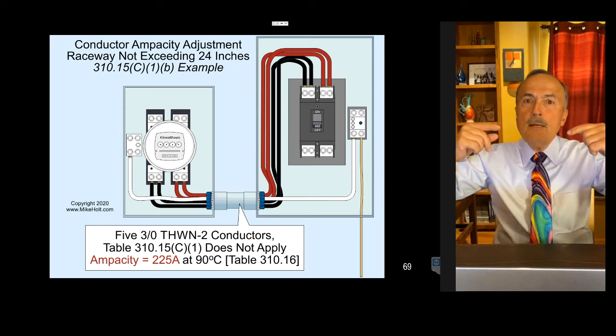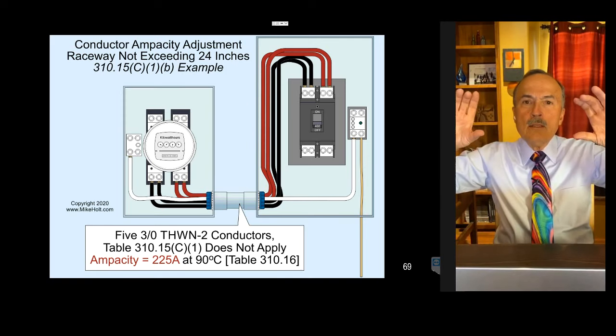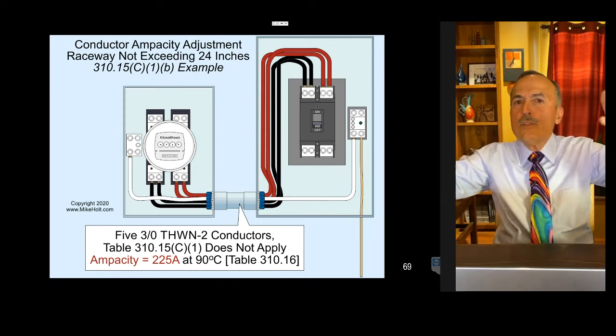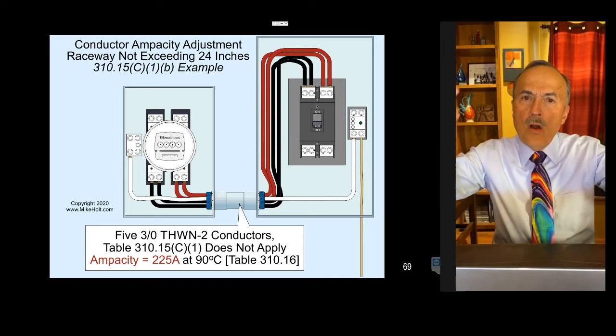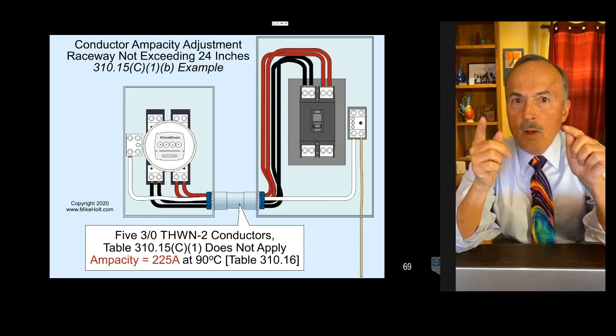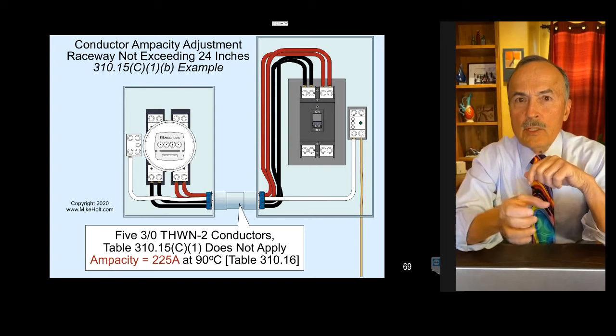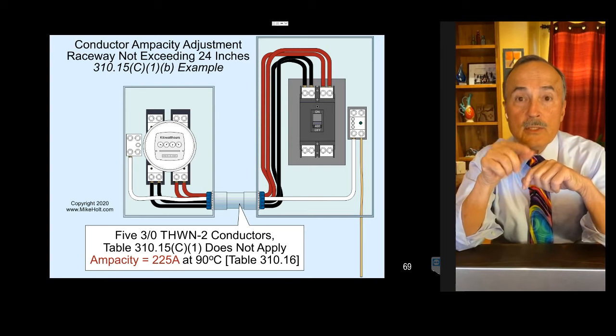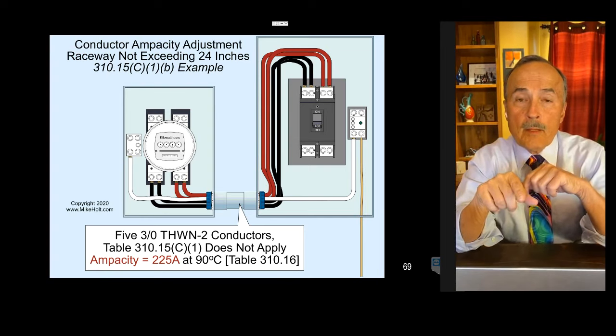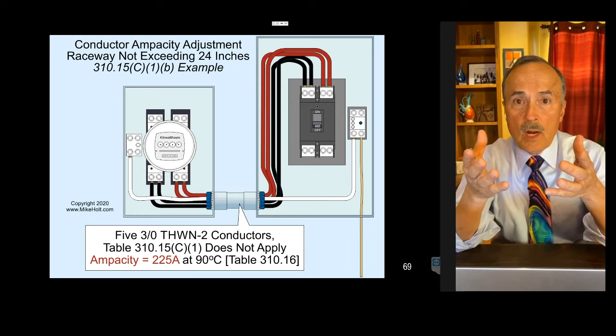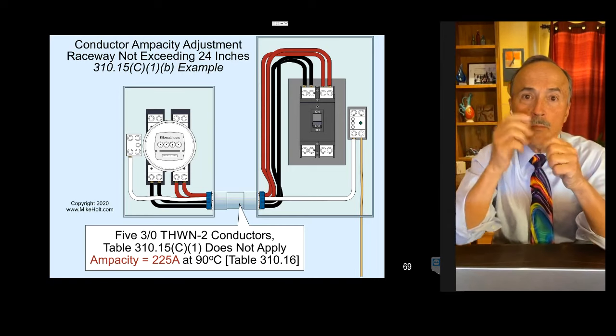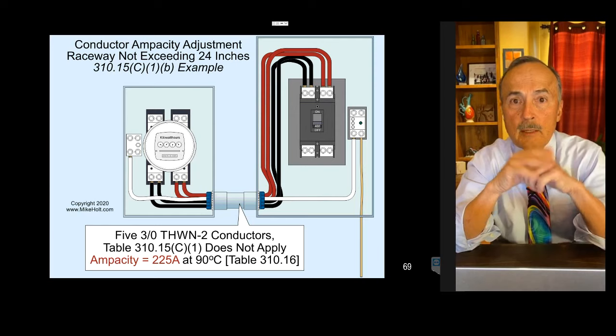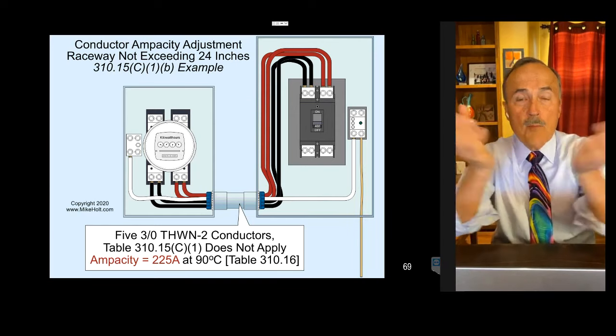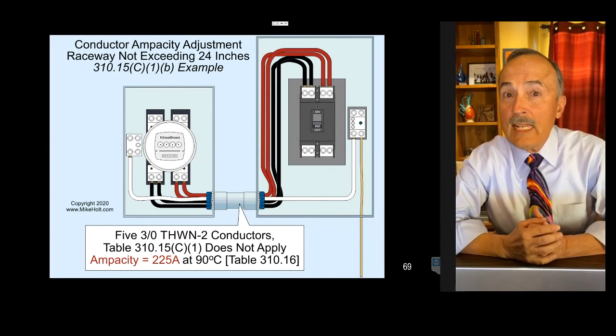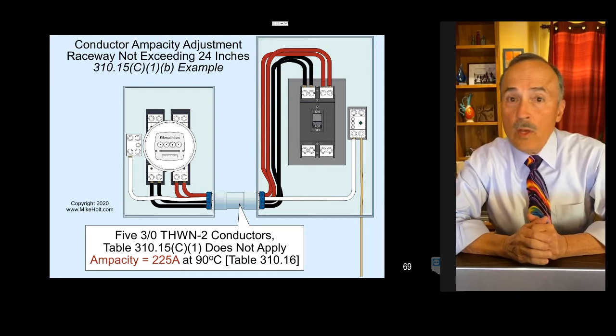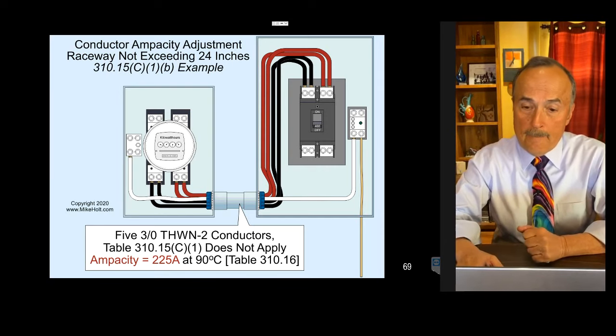Now, it's very common, let's say for services and nipples, wireways, where you want to try to get a lot of things. Another example is a lot of times I've seen contractors, my son did this when he did a medical job one time. They ran all the MC cables to the panel, but they went to a wireway, a little 4x4 wireway by, I don't know, 2 feet or whatever the case. They brought all the MC cables inside the wireway, and they had like a 2-inch raceway from the wireway into the panelboard. And of course, they didn't cut the conductors in the wireway.